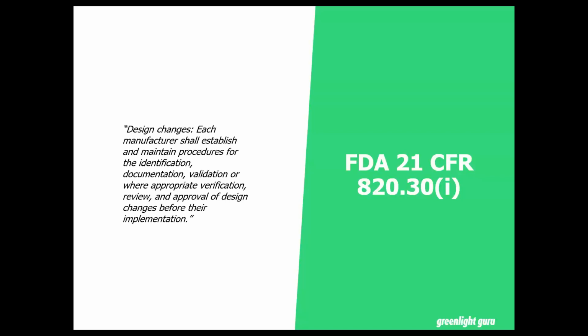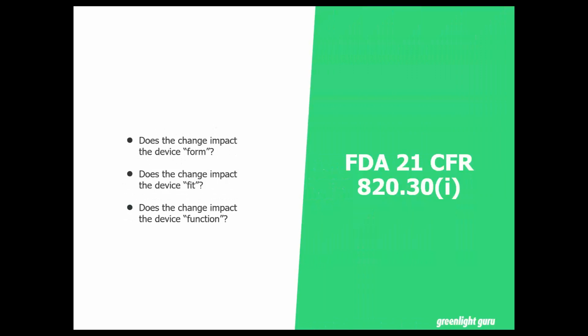I guess the regulatory framework for this, and we're giving some citations to FDA 21 CFR Part 820, specifically 820.30 with respect to design changes. This is also well defined and very, very similar within ISO 13485. The good news for you when it comes to design and development activities and design changes is that both FDA and ISO 13485 are very much in sync and alignment with one another. But the expectation is that you're defining your processes and procedures for when design changes happen and determining when design controls are impacted, when you need to validate and verify and review that type of information.